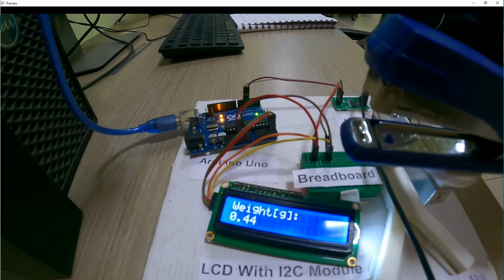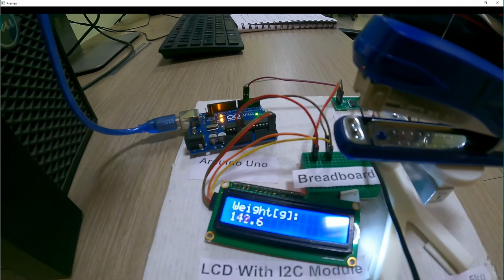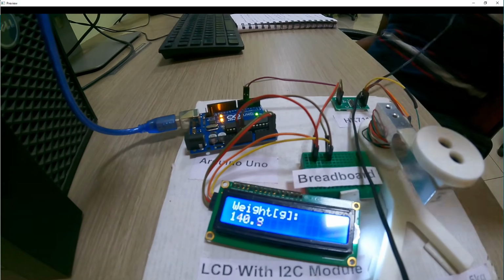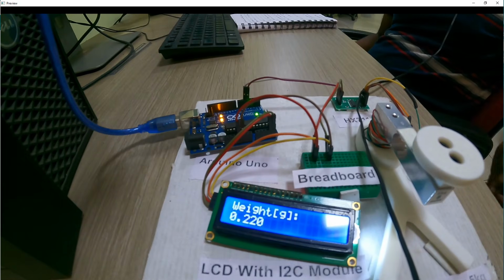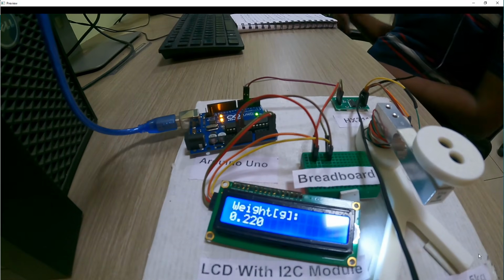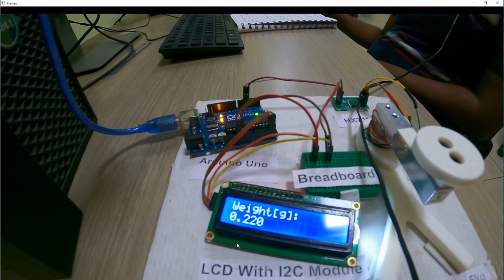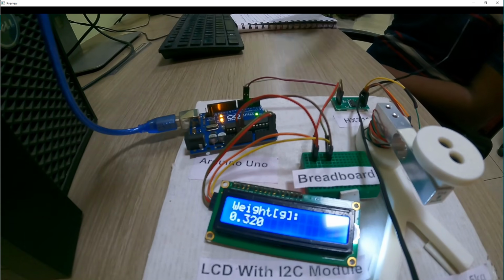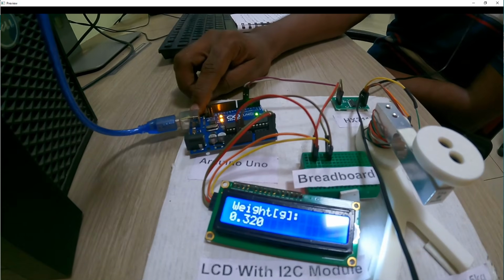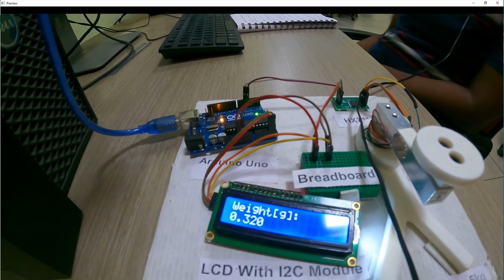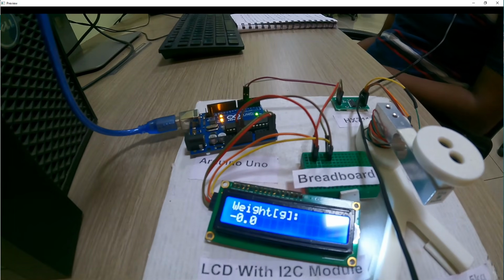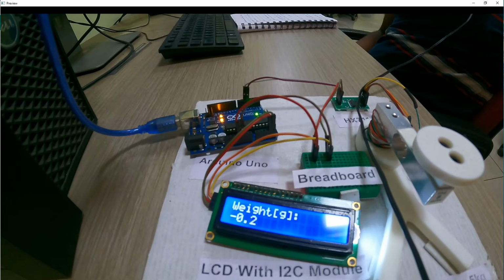This stapler is 140.42 gram, it is showing 140.9. So you can see that the error in all the cases is around 0.5 gram. That's because there is a zero error. So in order to restart and set the tare as 0, I can press this restart button next to this USB cable. If I press restart, it means the program restarts. So the dead weight is 0.